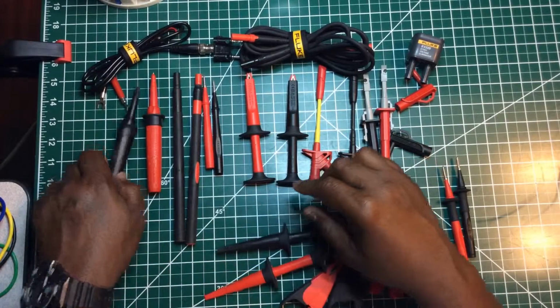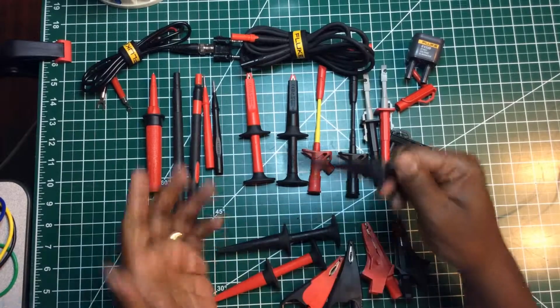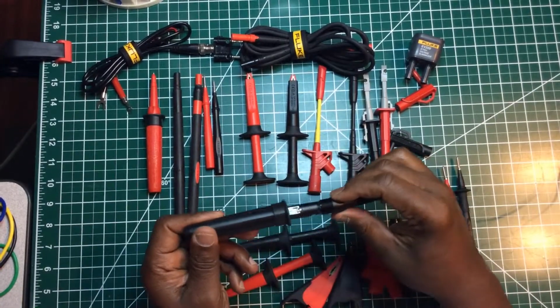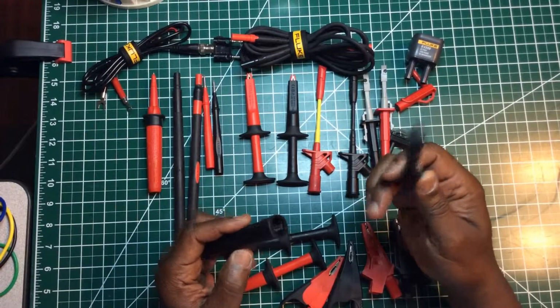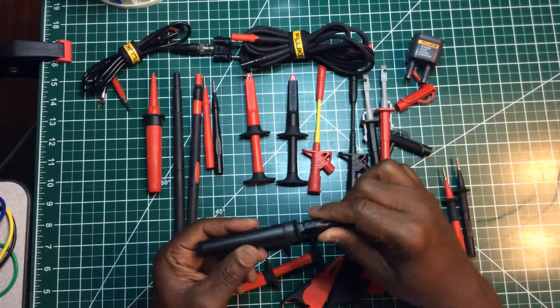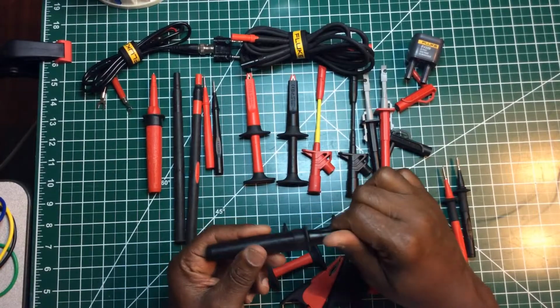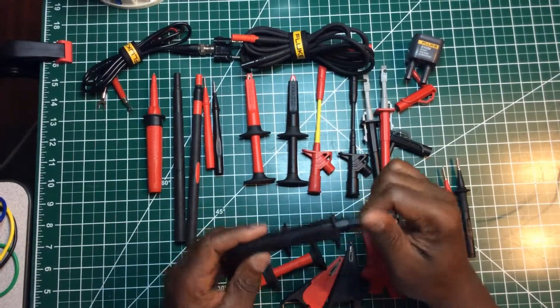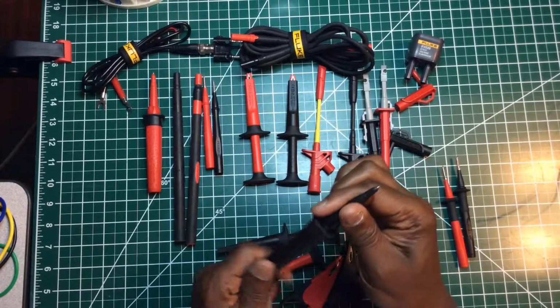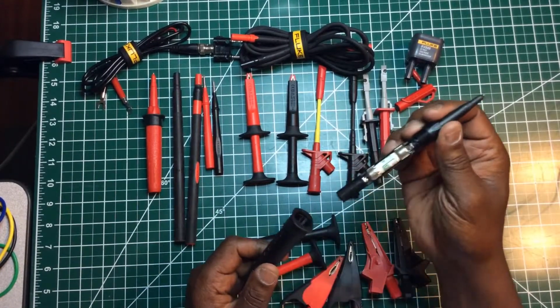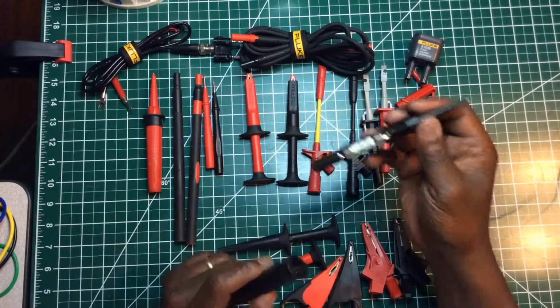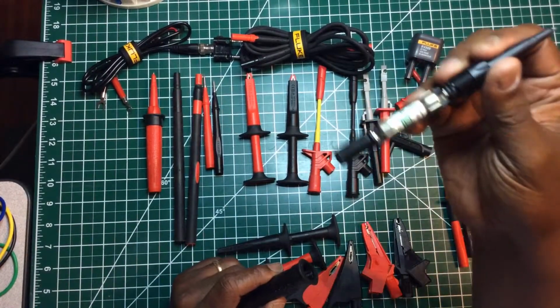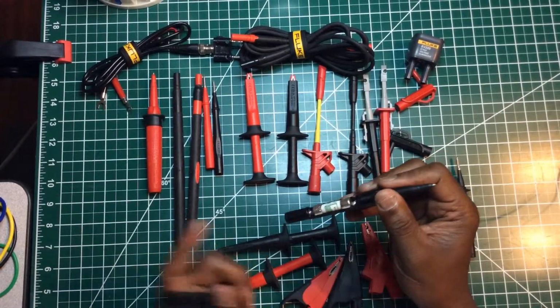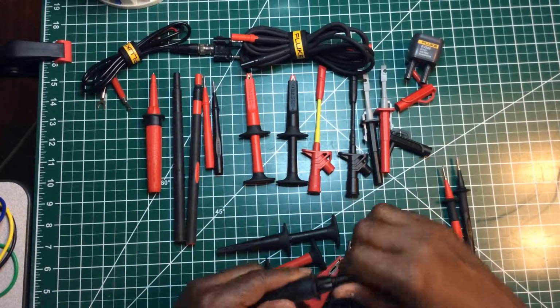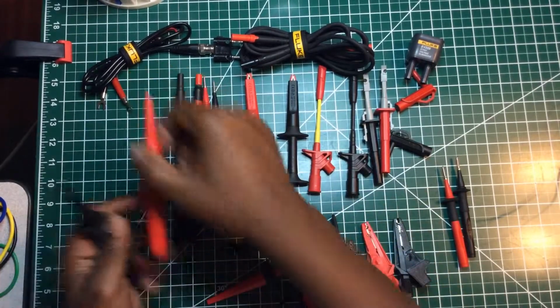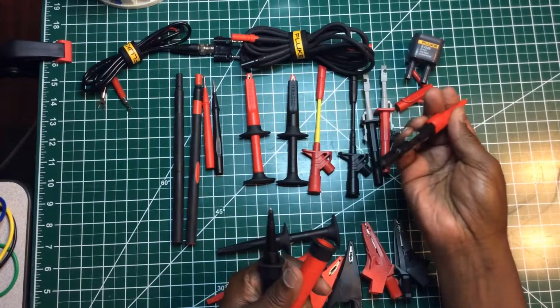These are the fused probes by Fluke, and I think all electricians should invest in these. A lot of people worry about whether the meter itself is fused, and they should, but I worry about myself too. They worry about the meter being protected, and that's a good thing, but I worry about me being protected also. This is the same size fuse that's inside the Fluke multimeters, so you can't go wrong with these, and both of them have it.